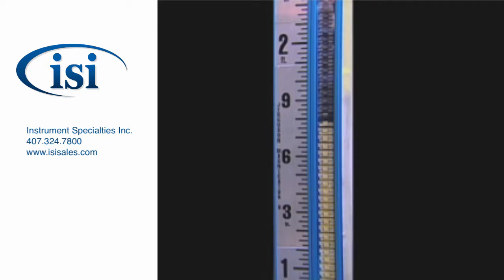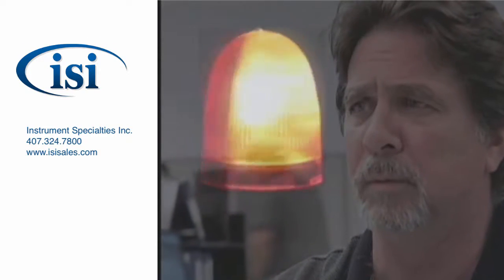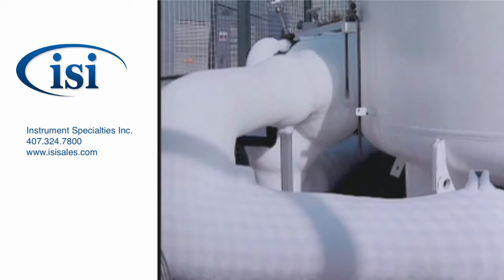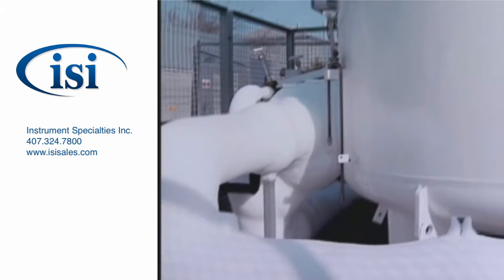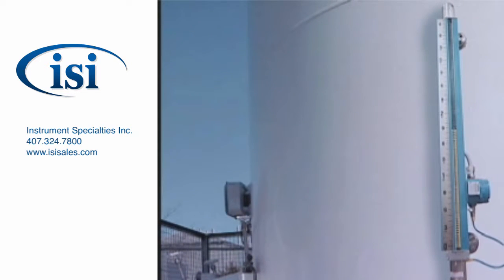If the liquid in your magnetic level gauge boils or flashes, you can forget about getting reliable level measurements for indicators, transmitters, or switches. How can this happen? It's a hot summer day. The liquid in your storage vessel is being maintained at a controlled cold temperature. However, the small amount of liquid within your magnetic liquid level gauge has warmed up to near or above its critical boiling point.